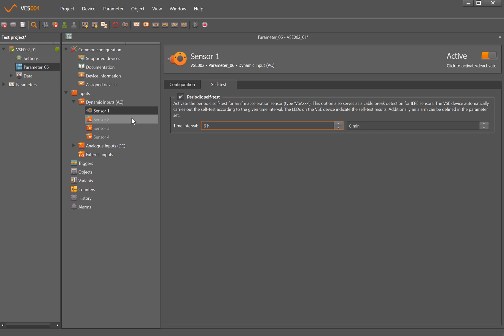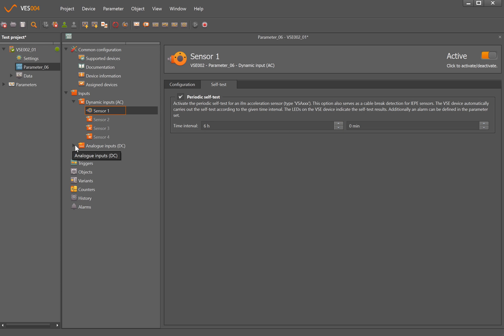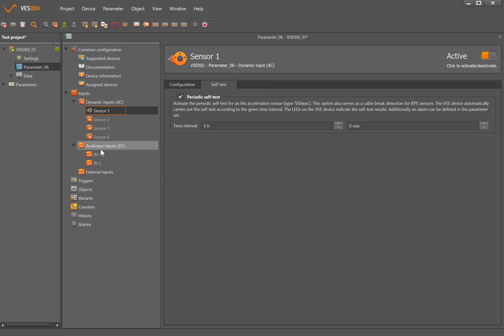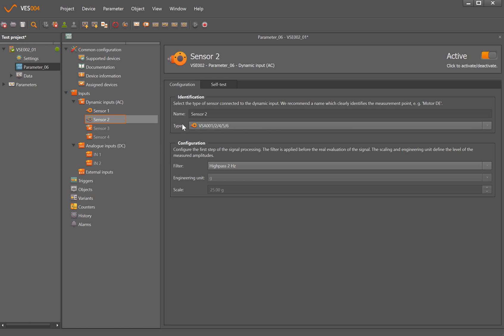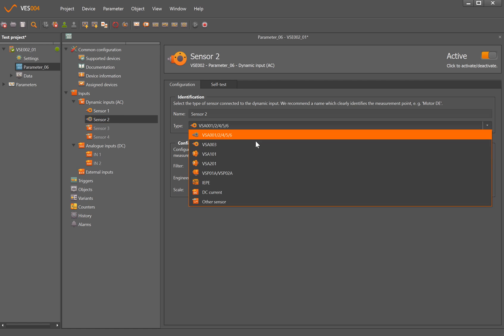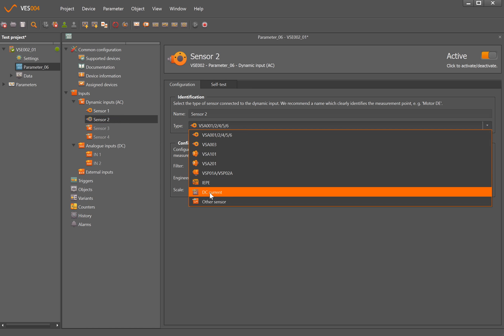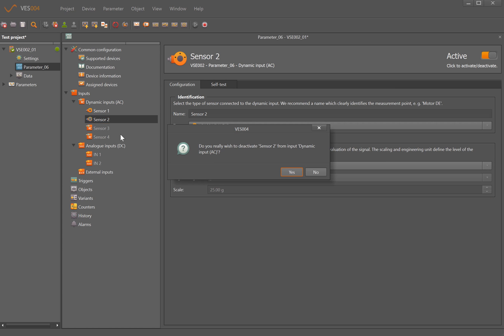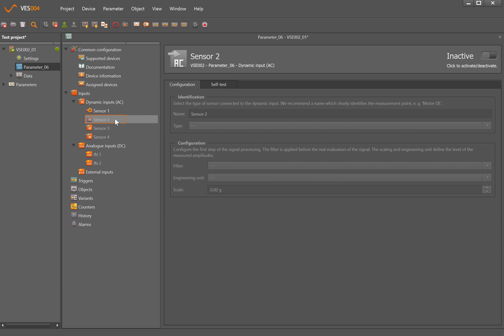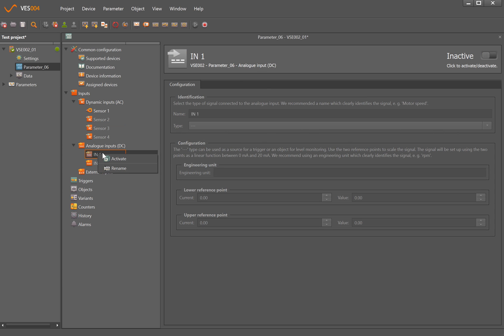So for my parameter set I'm just going to have one accelerometer input and I'm also going to have a temperature signal, so this would come in on the analog inputs in 1 and in 2. You could also have sensor 2, 3 or 4 as a 4 to 20 milliamp signal. If you want you would just activate it and then click down here DC current, but I have it wired into input 1 so I'll deactivate that and activate by right clicking on input 1.